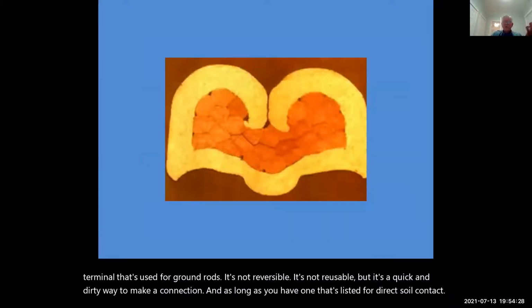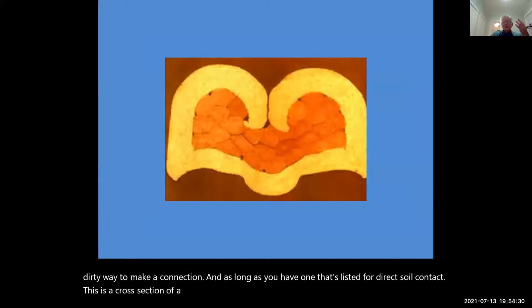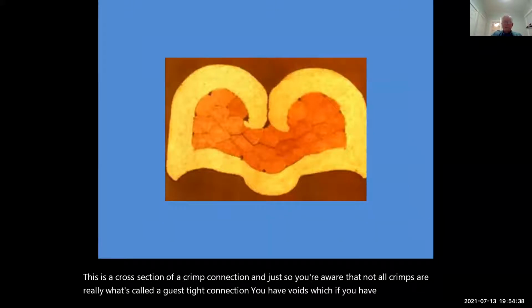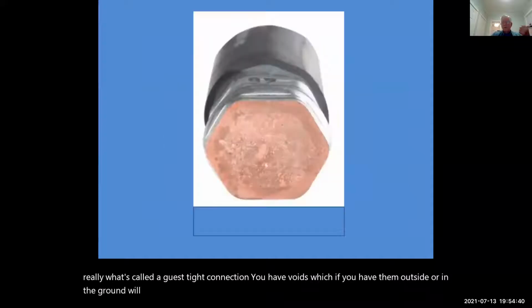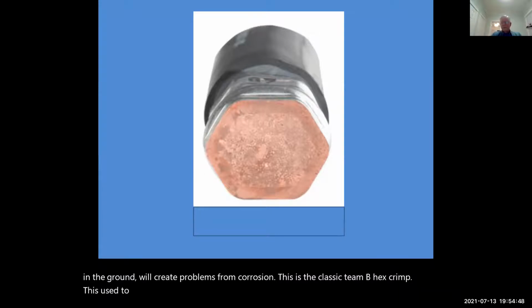This is a cross section of a crimp connection. And just so you're aware that not all crimps are really what's called a gas tight connection. You have voids, which if you have them outside or in the ground will create problems from corrosion. This is the classic TMB hex crimp. This used to be many strands of copper. It's all crimped into one. It's barely discernible as separate conductors. This is a truly gas tight crimp.